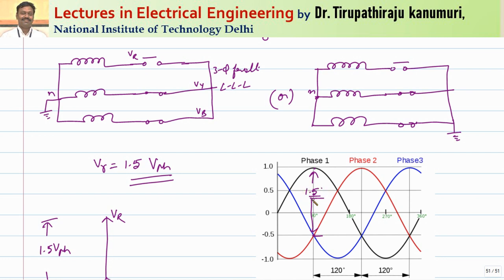Along with this active recovery voltage, transient oscillations also occur — also called the rate of rise of the restriking voltage — due to the circuit parameters of inductance and capacitance, which add on to this voltage wave to give the resultant value. These aspects are discussed in lecture number 205. I hope the effect of different circuit conditions and fault types on the recovery voltage, and why the maximum possible recovery voltage is 1.5 times the phase voltage, is now completely clear. If you still have any queries, please leave your comments in the comment section below. Thank you very much.